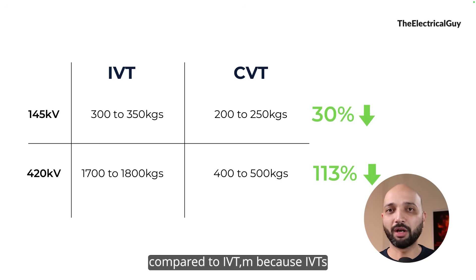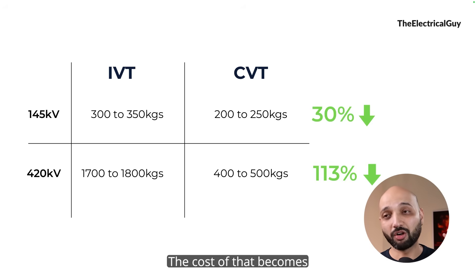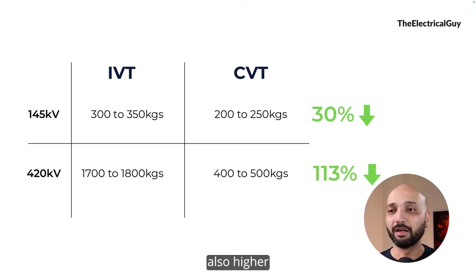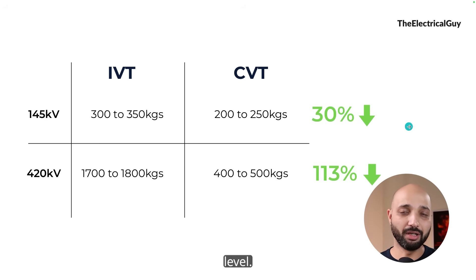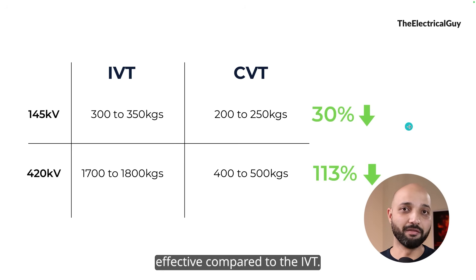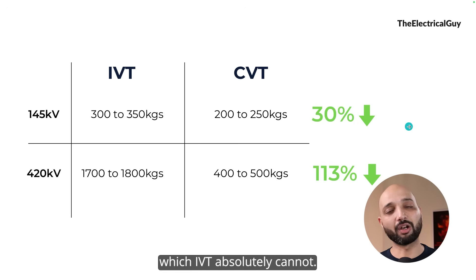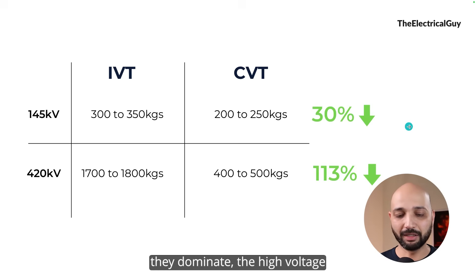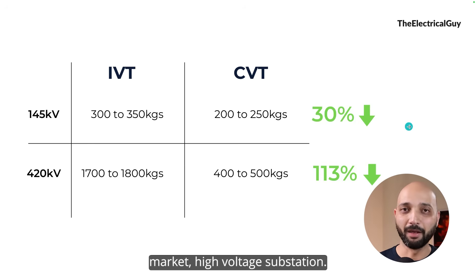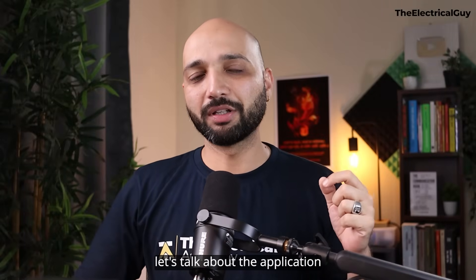Because IVTs require more material, more insulation, and more oil, their cost also becomes higher as we go up in voltage levels. For low voltages this is not a problem, but at higher voltages the cost of IVTs increases significantly, whereas CVTs are more cost-effective. And there is one additional advantage that CVTs offer which IVTs absolutely cannot — and that's why CVTs dominate the high voltage market, as we'll see shortly.